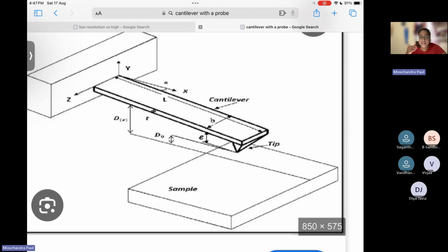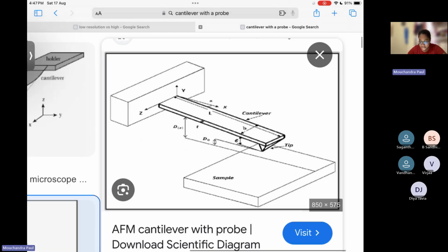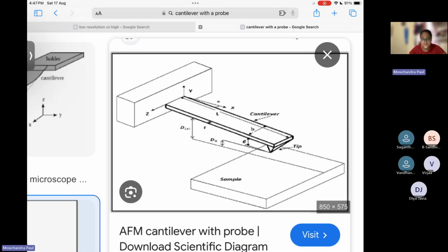And it can also allow other measurements, like it can also help you understand the stiffness of the surface. So if the material is very stiff somewhere, the probe will not go deep into it, right? If the surface somewhere is very soft, the probe will pierce, and the movement of the probe is held with this cantilever structure. And at the end, there's a detector that captures the motion of the probe. All right. This is the probe, cantilever with the probe. This is how it looks.